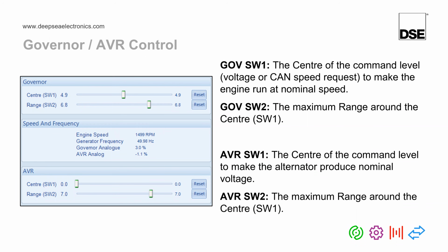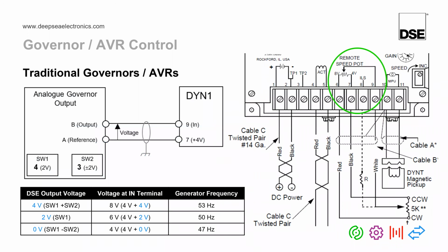I think, though, what is more important, which is a point I did forget to mention on the slide, if I just go back a couple of slides, you will see on the wiring here that we do advise that the cable be a shielded cable between the governor and the DeepSea module, or the AVR and the DeepSea module. This is just because any form of external magnetic interference, even if it's, for example, in the millivolt range, could cause disturbances with some governors and some AVRs, depending on how sensitive their input is. It doesn't have to be anything specially rated like CAN bus cable or anything like that, just high quality screened cable, maybe even the type you use for a magnetic pickup sensor, for example. That would be fine.